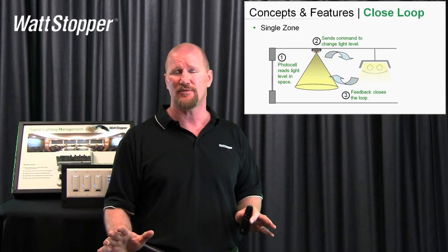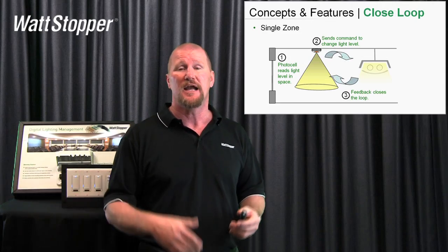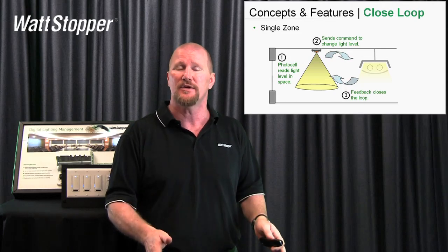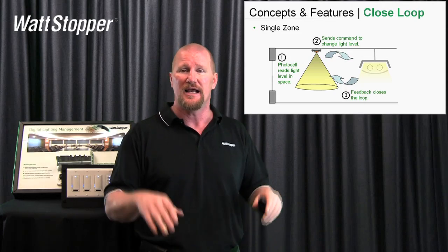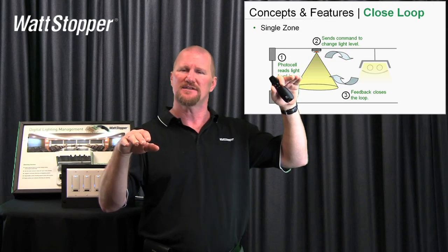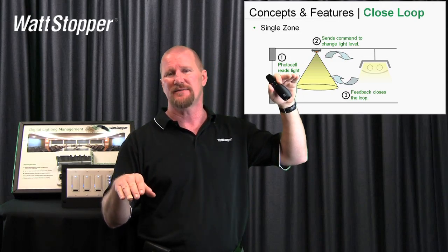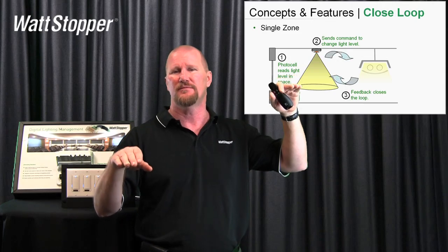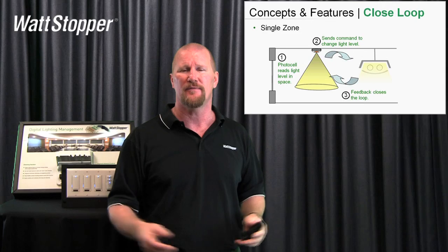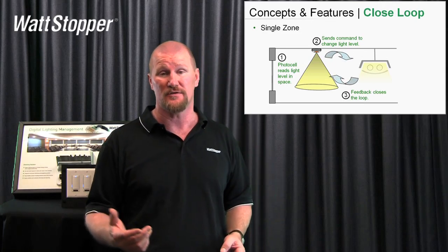Closed loop is really good for single zone applications, but not so great for multi-zone applications. The reason is that since the photo sensor is taking into account all the light that's entering, as zone one moves up, the photo sensor sees it and says there's a lot of light — maybe it should reduce zone two. Then it might say there doesn't seem to be enough light and ramp up. So you can get a sort of battle of trying to set the level, which is why we really recommend open loop for multi-zones.